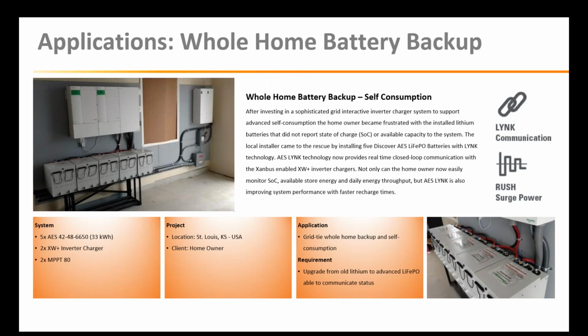Whole home. This is a whole home application, a very popular application throughout North America. It uses a number of inverters for very high surge capability, because the entire home is backed up, not just protection of certain circuits in the home. They're really looking at the surge capabilities there. It's a big deal. This particular customer swapped out another brand of lithium product because it had no communication, and he was unable to determine SOC and wanted to learn about and understand his batteries. So he did that by switching to a Discover product. Additionally, this moves him into the self-consumption possibility. So he really gets into tuning his system and essentially now taking it off grid and living without the grid, using the grid only as a backup. So really changing his dynamic of usage.